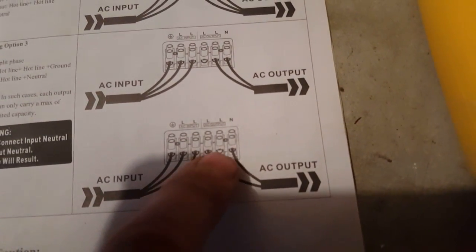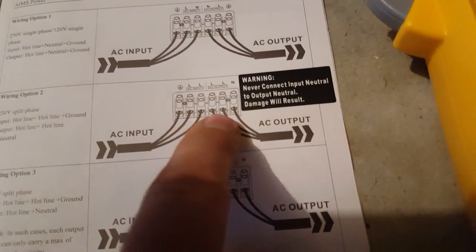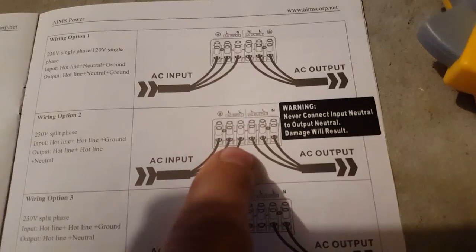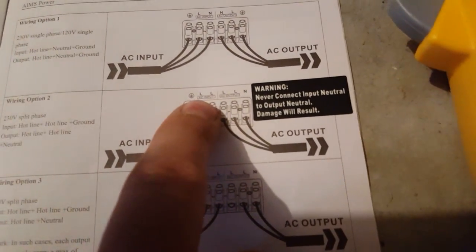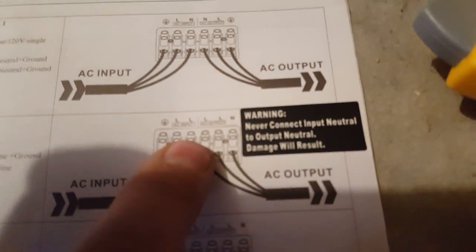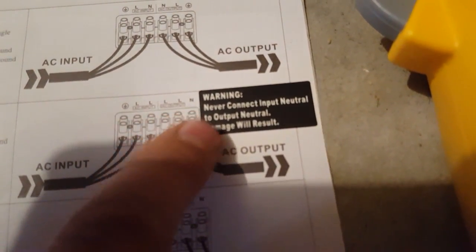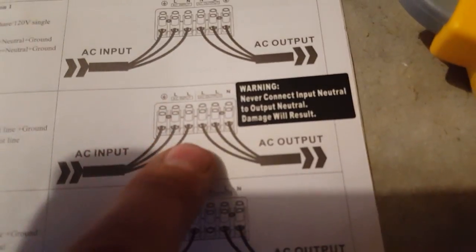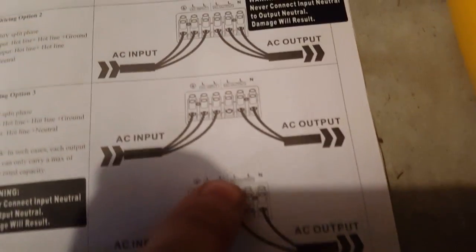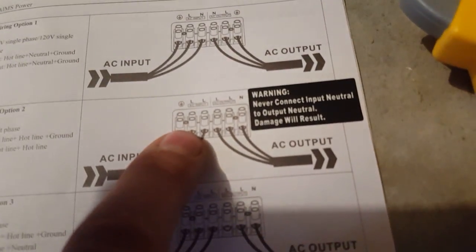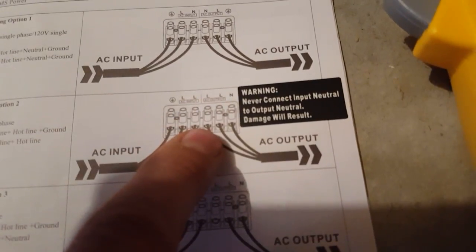You can see here it shows just one wire here. I didn't wire with this one, I wired with this one. So it's the same principle, you know, ground, leg one, leg two, leg one, leg two, neutral. This is the one I actually wired to. This will do 3000 watts, this will do 3000 watts, but this will do 6000 watts. The reason is you've got leg one, leg two, which is 240 volts.